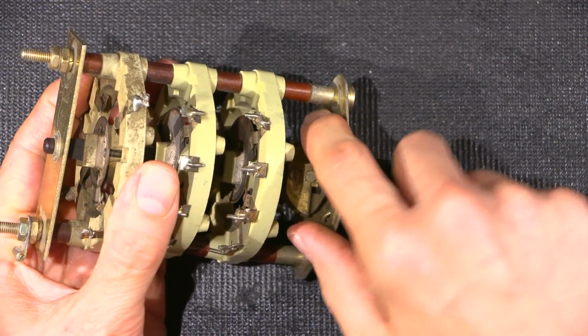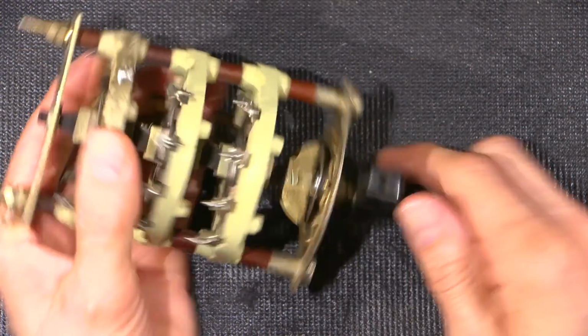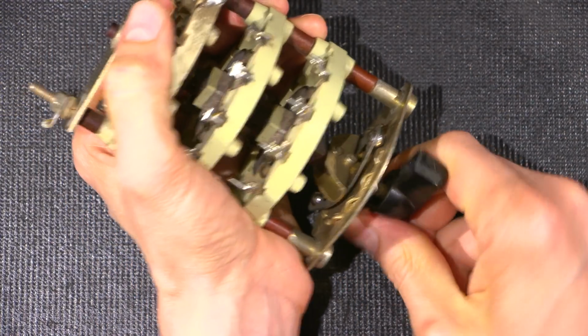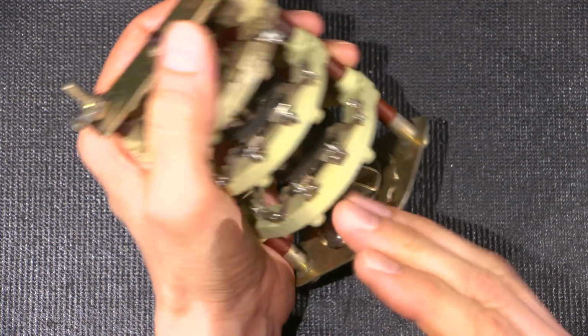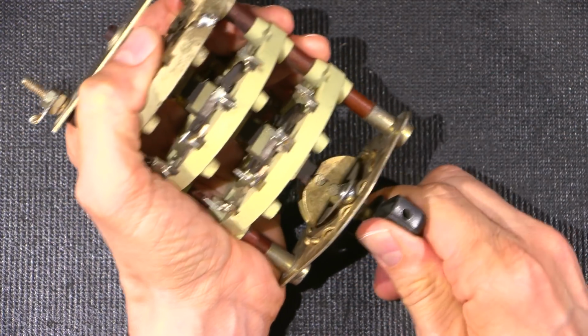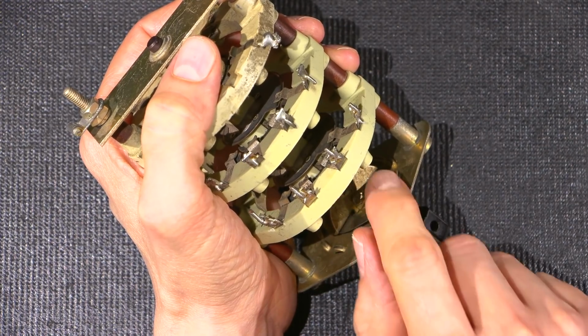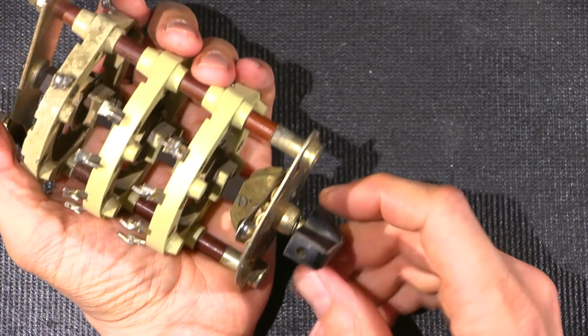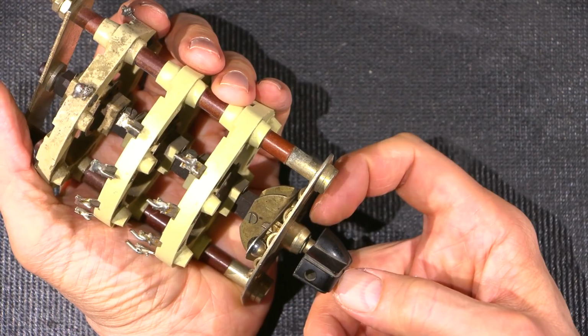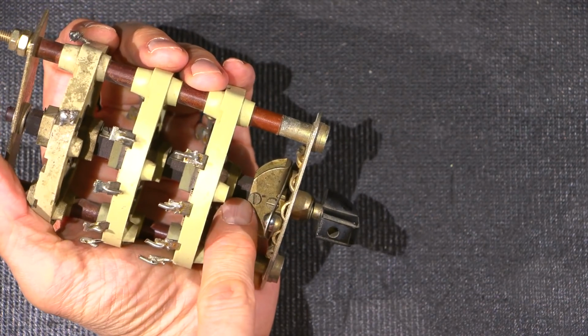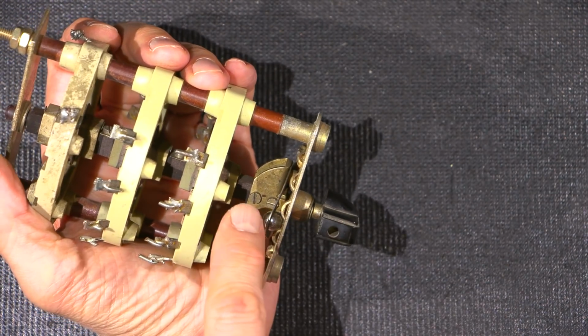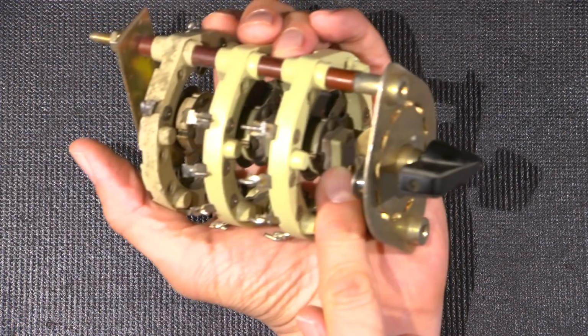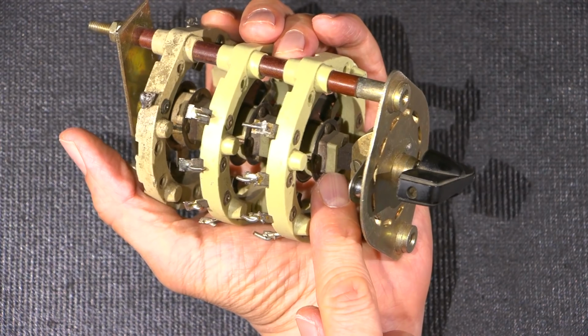Using that Spray and Stay in an area like this is very important because there's a ball that's going over. As you can see, it looks like little bumps here. And those little notches are what holds this in place. That's a thing that will wear, and same here with this area around the steel ball. You also want to get that kind of stuff in the shaft, but again, you want to be careful because you can see here there's a fibrous material. The actual center shaft is a fibrous material, and then there's a ceramic portion here. So this is designed for some very, very high voltage. So some things that you're going to want to keep in mind.